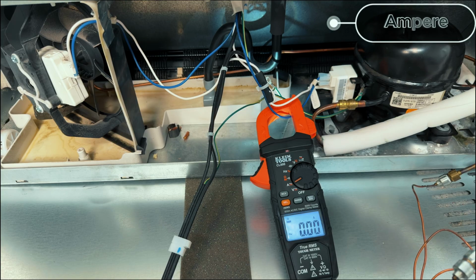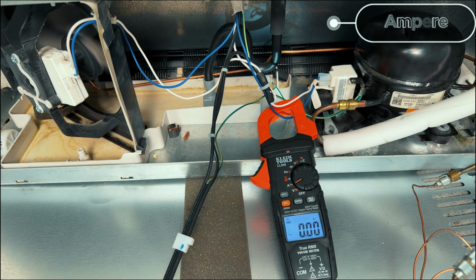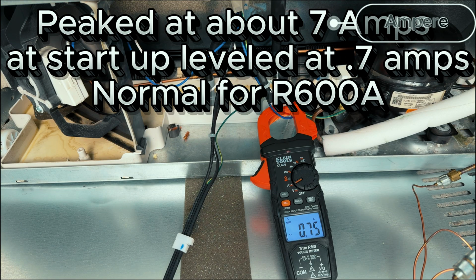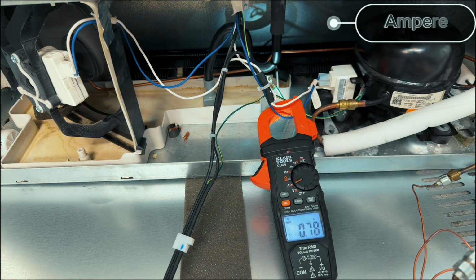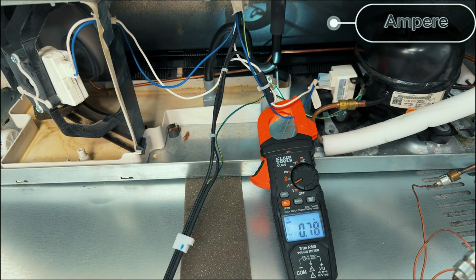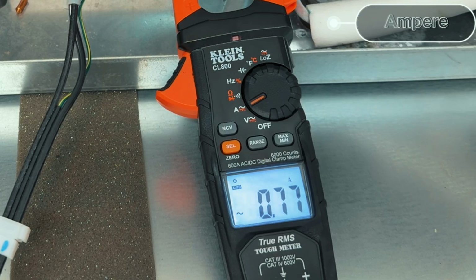All right, we got it connected to the compressor here on our live wire going to our compressor. Let's go ahead and crank this compressor on. All right, as you can see, we're getting about 0.8, 0.7 amps on that compressor. And because it is R600, this is going to be running on lower amperage.